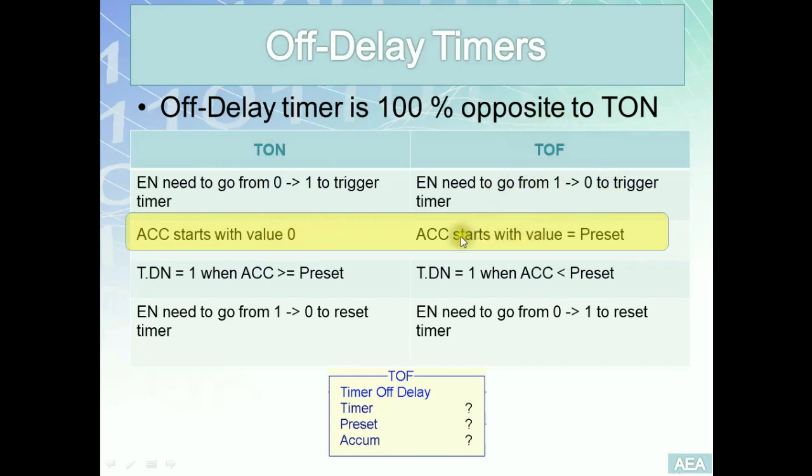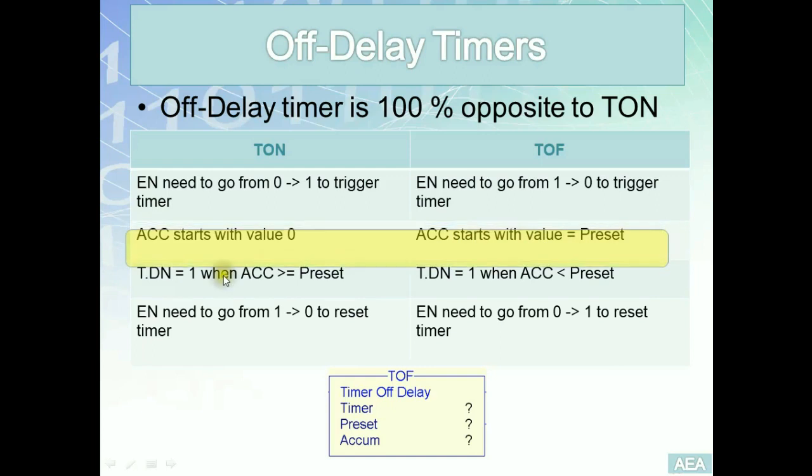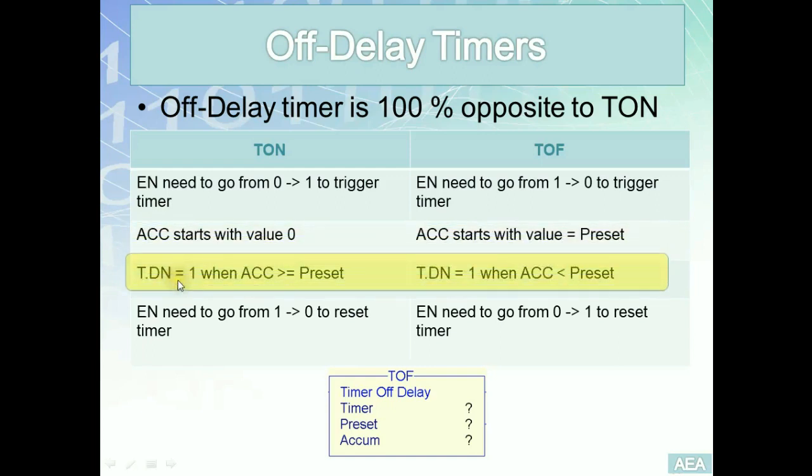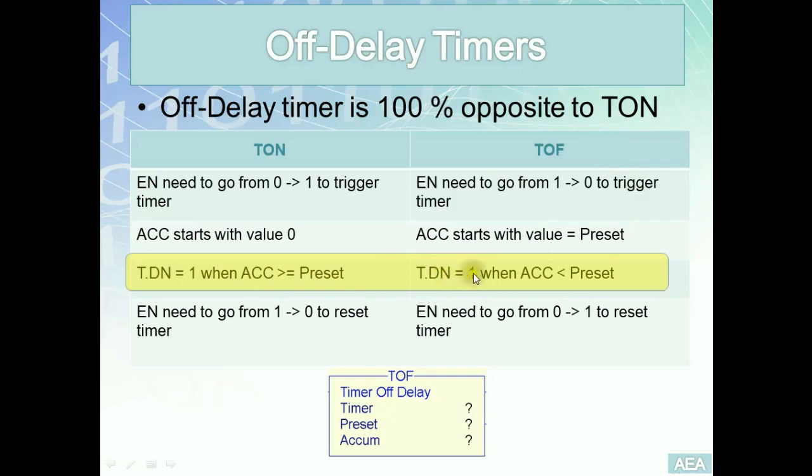On the other side for the TOF, once you put your PLC into run mode, the accumulator will start with initial value equal to the preset value. The third point: the done bit in the case of on-delay timer will go to one, will be set to one only once the accumulator hits the preset value.